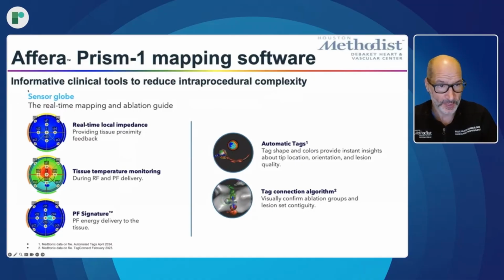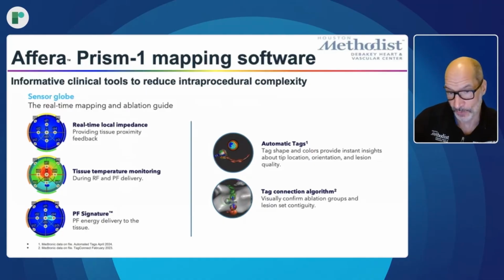It displays the sensor globe, a schematic of the sphere catheter showing the location of the 9 mapping electrodes that provide real-time local impedance measurements as a guide to contact. Because these electrodes are in the same location as the thermocouples, they're used for temperature monitoring during RF and PF delivery. And it gives you a signature of the PF delivery to the tissue. In the mapping, it creates automatic tags. If you complete the delivery without moving, you will get an automatic tag. And it has a built-in tag connection algorithm that informs you, when you're delivering a linear lesion set, whether your consecutive lesions are adjacent to one another. And you can configure the distance that you're willing to tolerate.